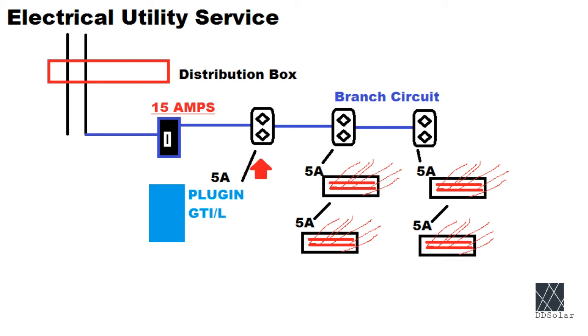Actually this is incredibly dangerous. What the grid tie inverter has done is literally defeat the circuit breaker. In the diagram you can see that the circuit breaker is now showing a current of 15 amps so it's not going to trip. However there are four 5 amp heaters plugged into the wall drawing a total of 20 amps. The grid tie inverter is providing 5 amps. The circuit breaker is providing 15 amps.